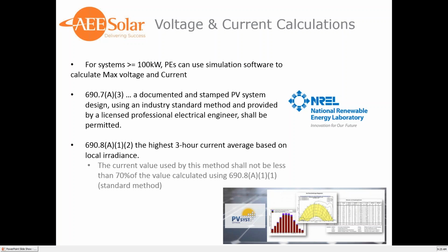Voltage and current calculations. This is what I talked about briefly with the 690.8, but this is another means for calculating this. For systems greater than or equal to 100 kW, professional engineers can use simulation software to calculate max voltage and current. So 690.7 allows us to use either the table in 690.7 for the voltage correction, or the manufacturer temperature coefficient on modules with the low temperature, and now adds other provisions for using simulation software to actually model the system and look at the maximum voltage that they will see on the system. So it's possible for larger commercial systems that you may be able to get an extra module out of this to help reduce stringing, labor, whatever else comes with that.